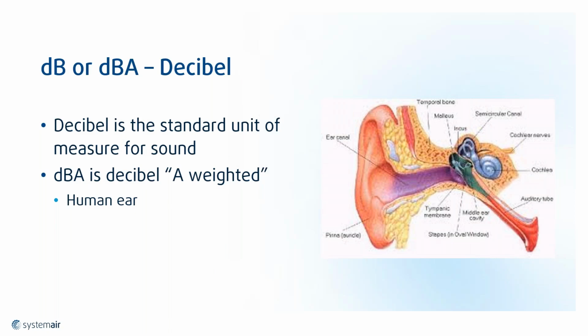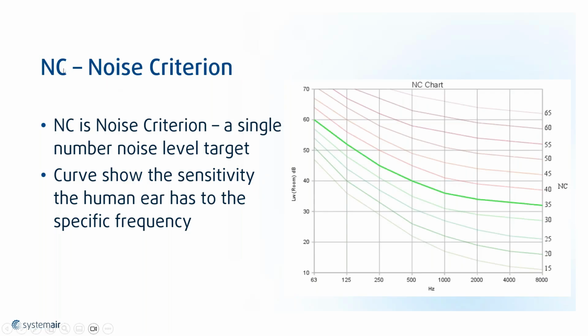So dBA, how we measure it. A lot of us are engineers on this call. Decibel is the standard unit of sound. dBA is A-weighted, for the human ear. And then there are different things as well. ASHRAE, in the Refrigeration and Fundamentals handbooks and the HVAC Applications handbook, talks about NC, noise criteria. Noise criteria is a single number, a noise level target, so you're not dealing with different frequencies and different decibels and different ranges. It's just a single number that you can apply to HVAC equipment, for example. There's also RC, which is room criteria.